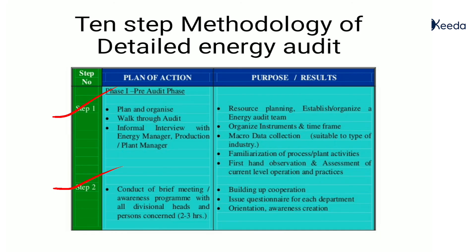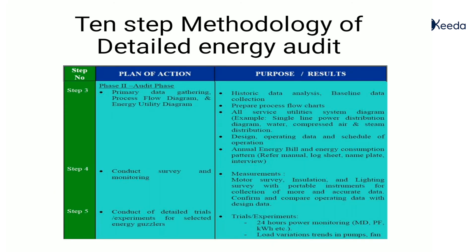Step 5 is the conduct of detailed trials or experiments for the selected energy end-uses. Here, 24-hour power monitoring is done, load variation trends in pumps and fans are recorded, boiler efficiency trials are conducted, and furnace efficiency trials are conducted.